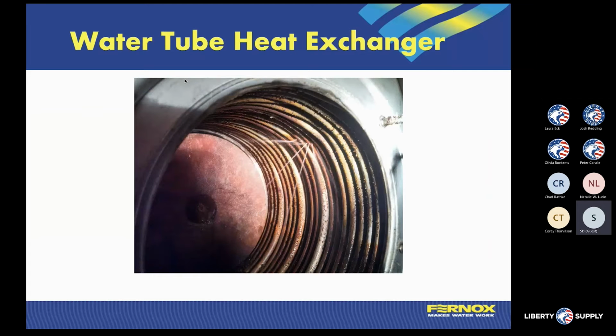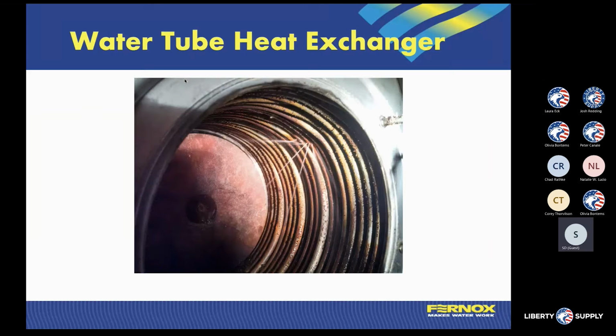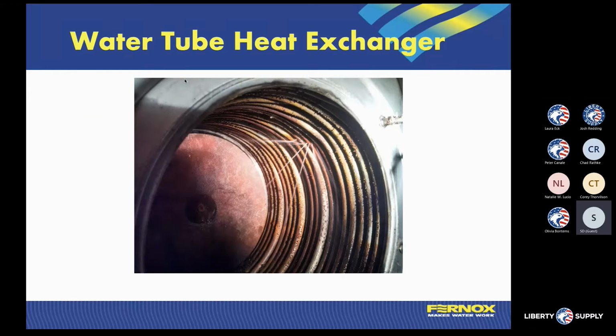When we start to overheat heat exchanger tubes from the burner side and we have sediment on the opposite side, those heat exchanger tubes will start to expand and contract. Eventually, you will end up having pinhole leaks in heat exchangers and different other components, leaks from that standpoint. So obviously from a heat exchanger standpoint, this is a place where we're starting to see more issues with heat exchangers being denied, because this is not a failure of the heat exchanger.